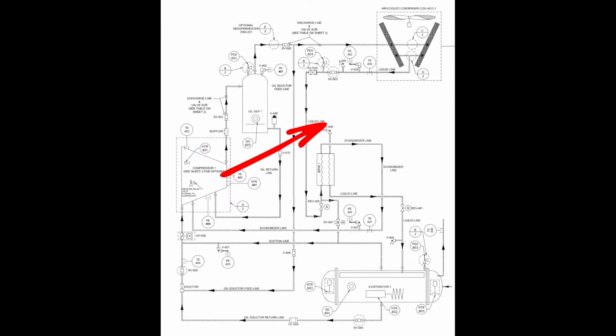All right, so we have this brazed plate economizer. This means that we're no longer using flash gas or a flash tank in order to have our economizing. What we're doing instead is we are taking this liquid leaving this condenser, which is already subcooled to a degree, maybe 5, 10 or so degrees. And then as we come into the brazed plate economizer, this is where we start feeding back to the evaporator, right?